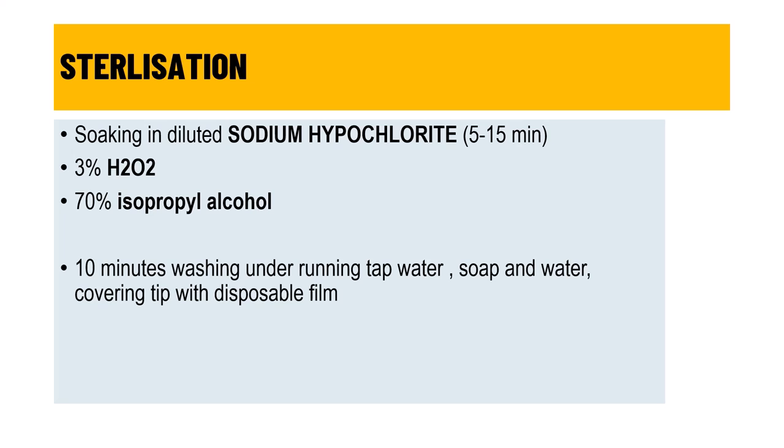Disadvantages include dependence on corneal thickness causing over- or underestimation, altered readings in patients who have undergone refractive surgery, higher cost than the Schiotz tonometer, lack of portability, and the need for sterilization between patients. Sterilization can be done by soaking in diluted sodium hypochlorite for 5–15 minutes, 3% hydrogen peroxide, 70% isopropyl alcohol, 10 minutes under running tap water with soap, or using disposable tonometer tips. However, disposable films do not provide adequate protection against prion disease.